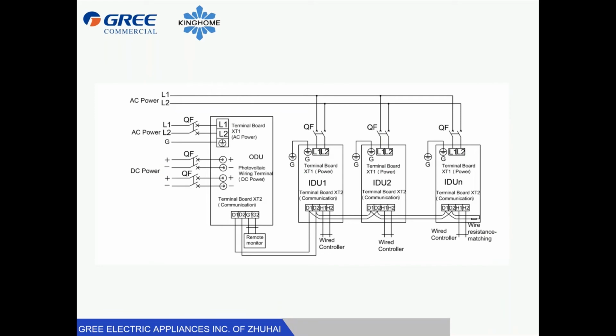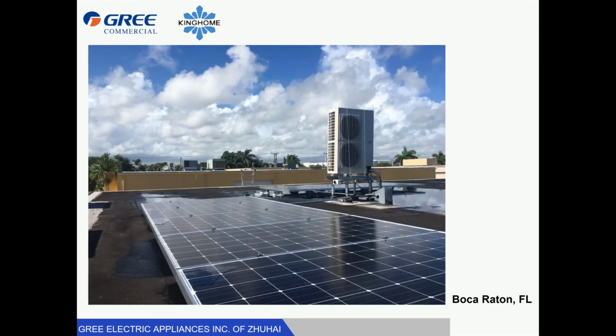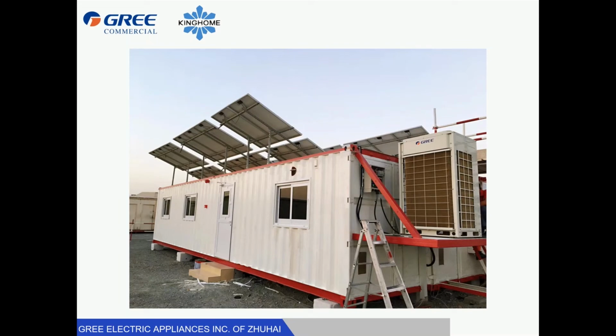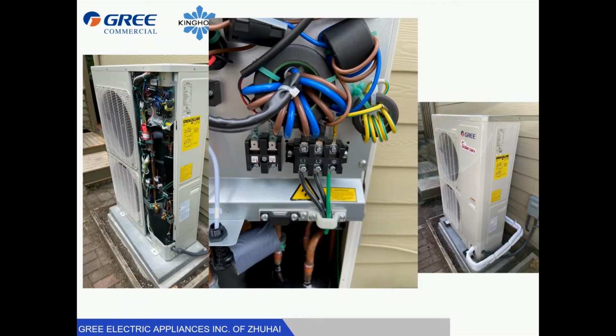So here's the wiring diagram that shows the AC power connects to the L1 and L2 terminals, and the DC power connects to the QF terminals right there on the terminal board. And I've got a picture coming up here that shows what it looks like in real life. So here's a picture of an installation down in Florida. Here's another installation of a job shack trailer. This one has only solar panels operating the entire building, and all the solar power is going through the VRF unit.